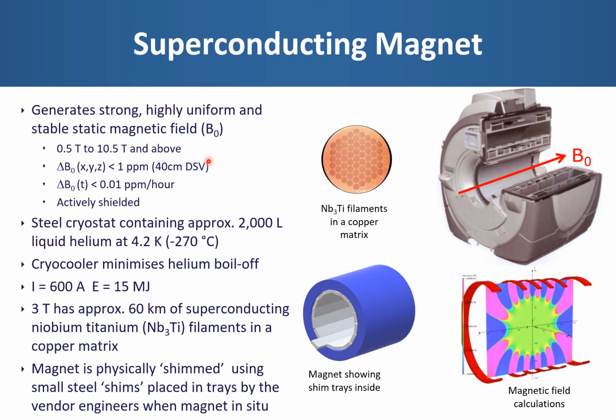Magnets have very good spatial uniformity, less than 1 part per million variation over a 40 centimeter diameter spherical volume within the middle of the magnet. They also have a very good temporal stability. And to minimize the extent of the 0.5 millitesla fringe field, they are also actively shielded.